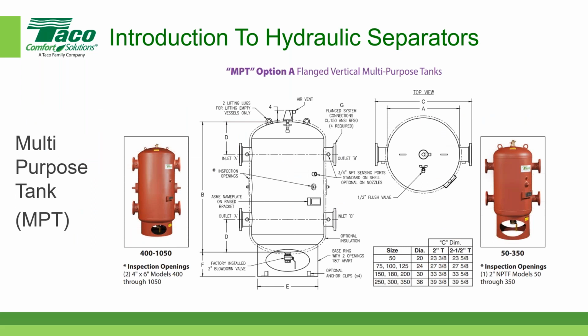And this other device here is called a multi-purpose tank, MPT. And one of the ways that you can get a multi-purpose tank is as a hydraulic separator, a combination air and dirt separator, all in one device. The way this particular one is piped up, you can see it has 4 connections. There's the primary, let's make this the primary side in and out.